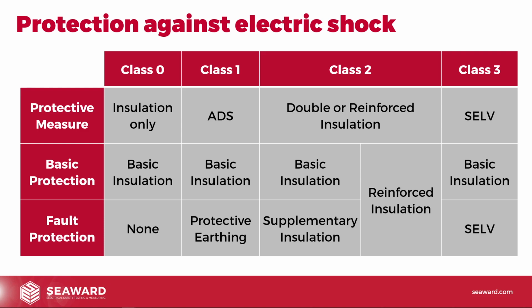Now, for Class 2 equipment, we use double or reinforced insulation. So the normal double insulation, we've got basic protection provided by basic insulation, and the fault protection is provided by supplementary insulation. We've got even more insulation protecting us from the live part. So even if the basic insulation were to fail, we've still got more insulation before we could come into contact with the live parts. We could do the same, as we mentioned before, with a single layer of reinforced insulation, as long as it's got the same properties of 2 layers of basic and supplementary insulation.